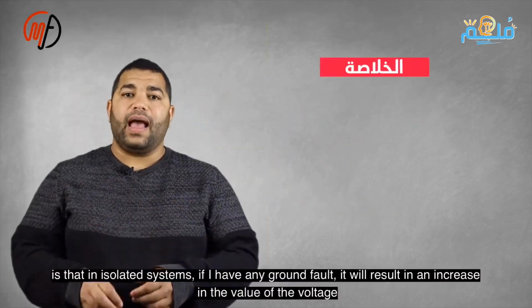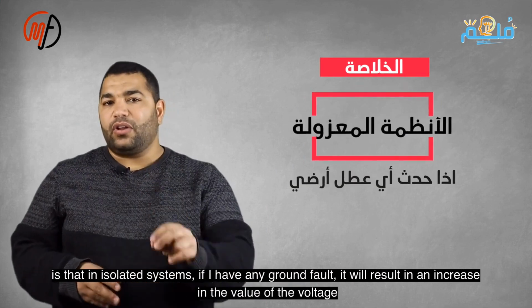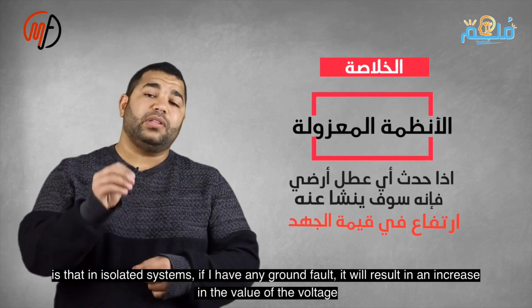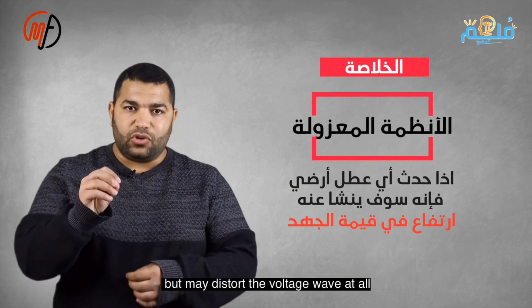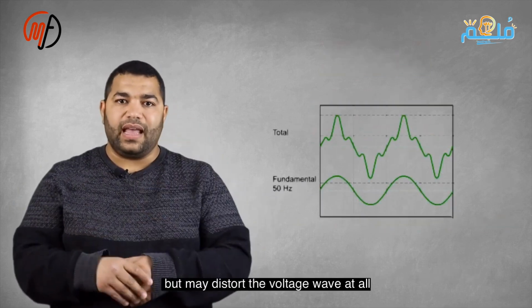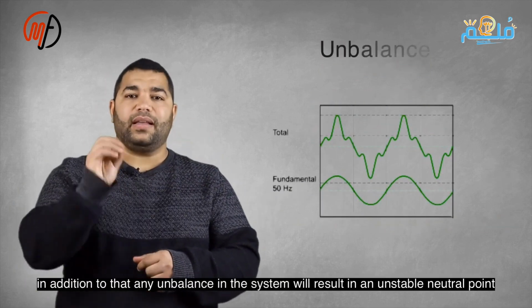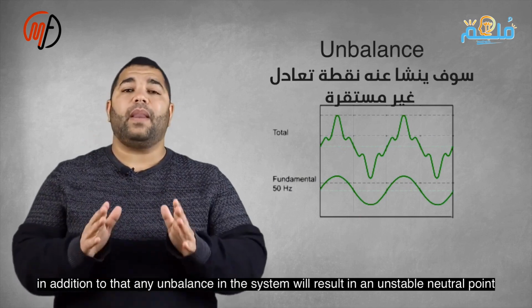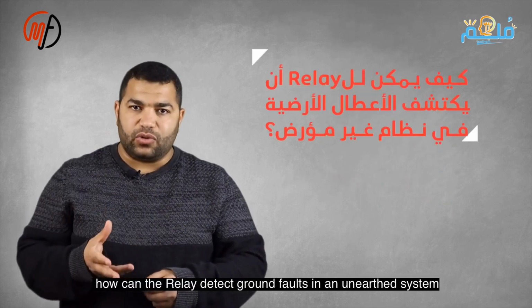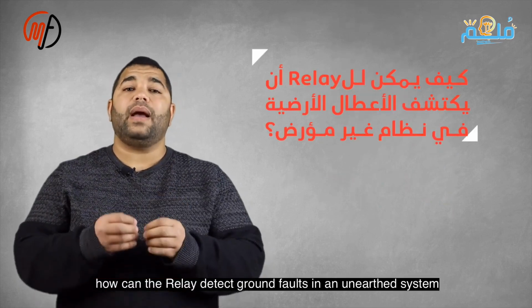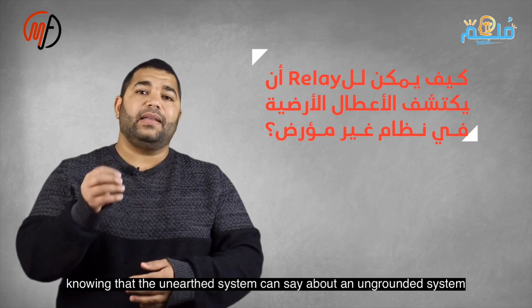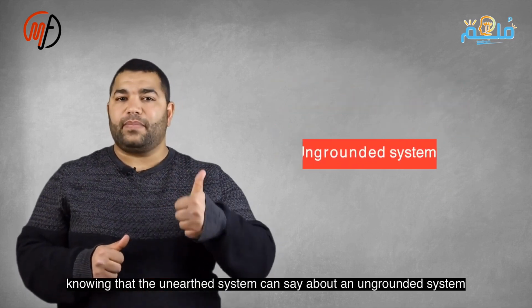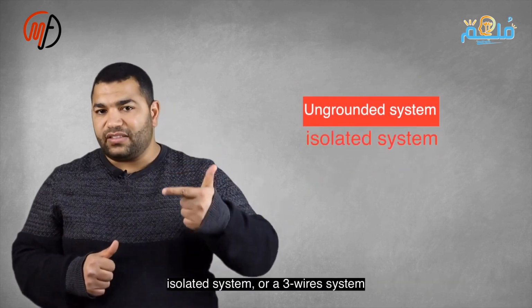In summary, in isolated systems, if a ground fault occurs, it will result in a rise in voltage levels, and may even distort the voltage waveform. Additionally, any imbalance in the system will create an unstable neutral point. So in this case, how can the relay detect ground faults in an ungrounded system, knowing that the ungrounded system can be referred to as an isolated system, or a three-wire system?